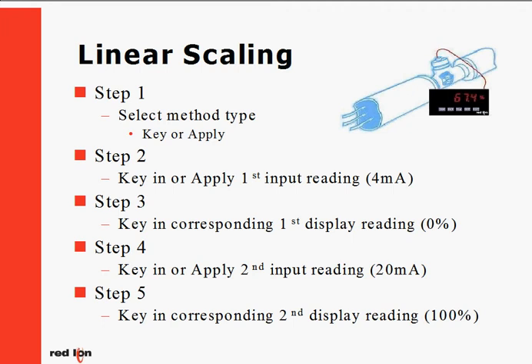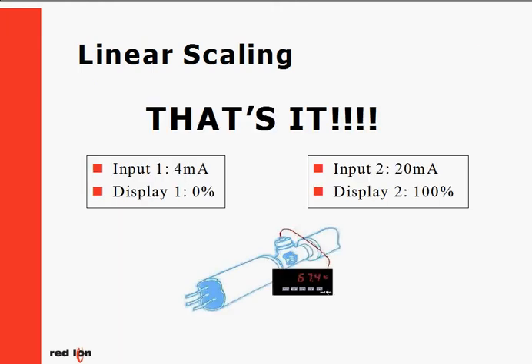In step 4, we keyin or apply our high point input value. In our example, we would enter 20 milliamps. The final step has us keyin the appropriate display value corresponding to our high point display value. In our example, that is 100 percent. Scaling is now complete — no math calculations. All we need to perform linear scaling is four values: low and high input values, and low and high display values.